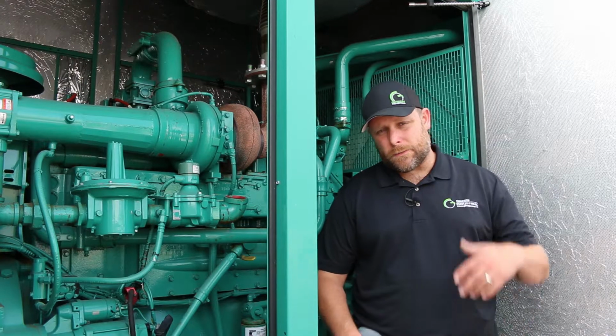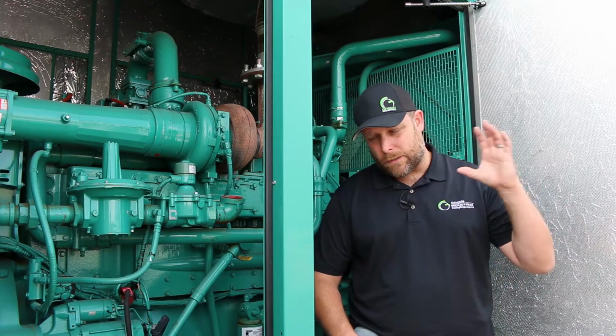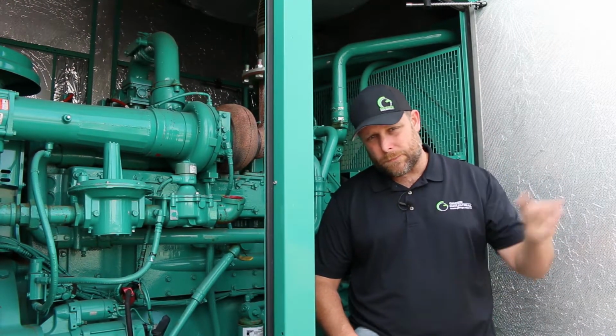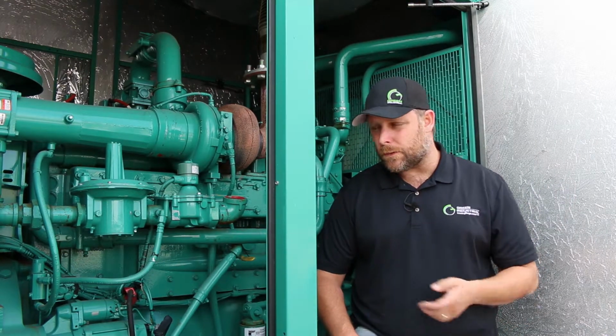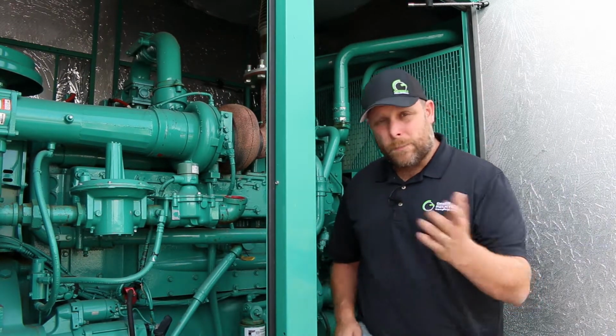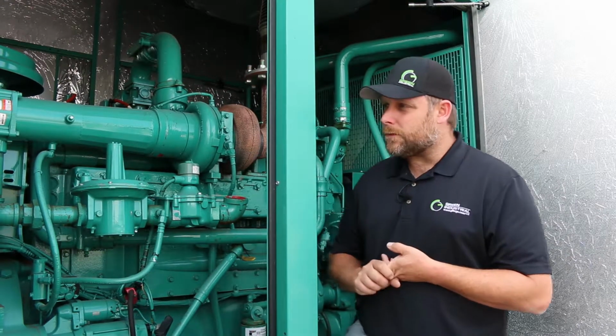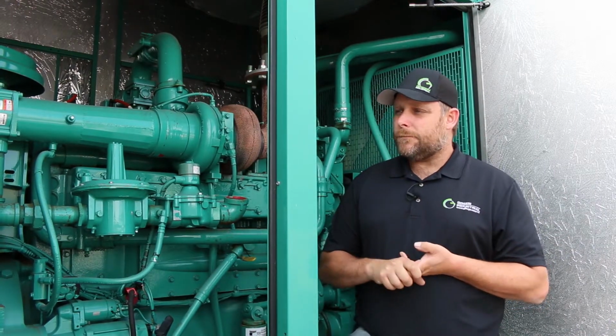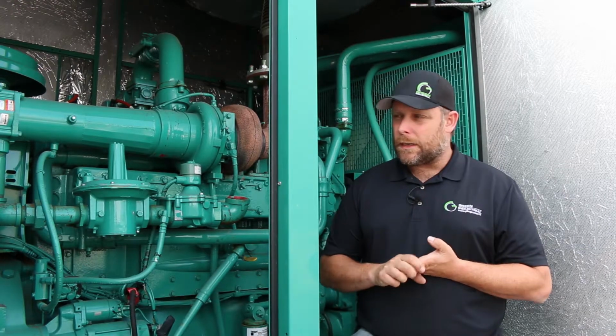Now that it's going to be 480 volt, likely that's not going to be the case, because the load bank is a single phase load bank and that transfer switch is going to be too many amps from a voltage standpoint now. So this thing here, we could package it with a different used transfer switch, possibly quote you a new ASCO transfer switch, and we could always get you a load bank, though rarely do we sell them anyway.